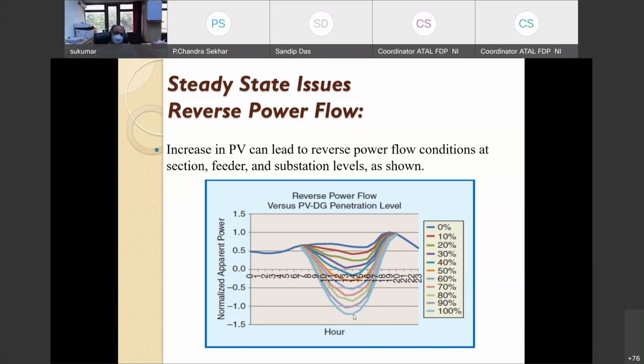As a result, you can see here the ramping up from the afternoon to the evening is very large as against the ramping up that is there in the normal scenario. Because of this, there is a challenge in the grid integration of rooftop solar systems, and many a times we keep it around this so that reverse power should not happen in the distribution line. If the reverse power happens, that means if the power crosses the transformer, then our protection scheme will get jeopardized, because the protection scheme is not designed to handle the reverse power condition.